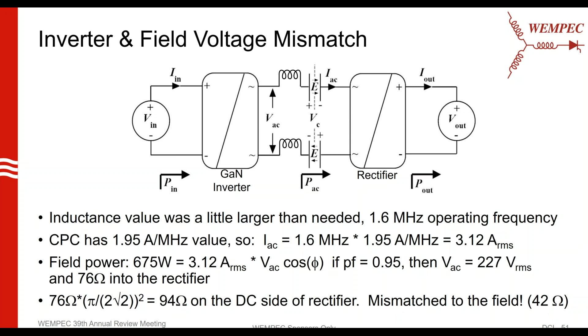That means our impedance looking into the AC side of the rectifier is 76 ohms. If we reflect that 76 ohms from the AC side of the rectifier to the DC side, that's 94 ohms. But the field winding is 42 ohms, so there's a mismatch, and we have to match these impedances.